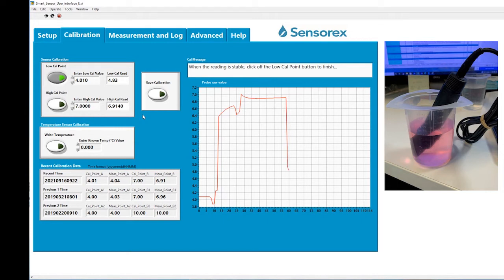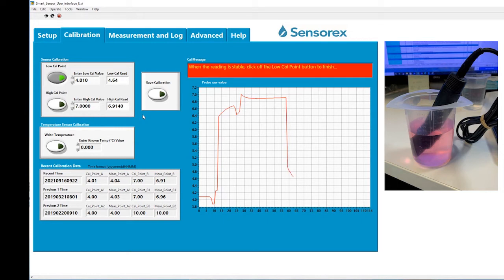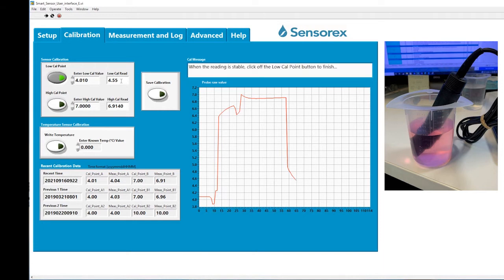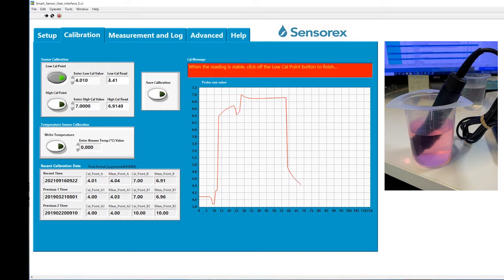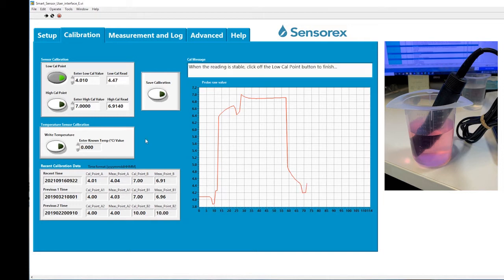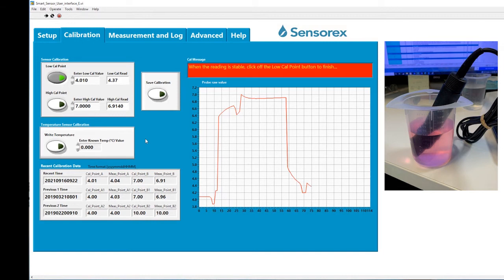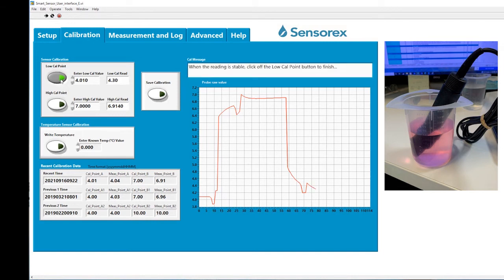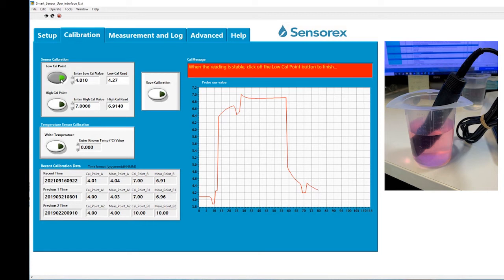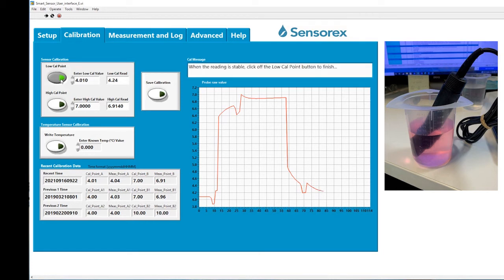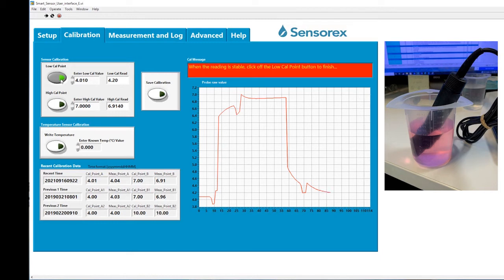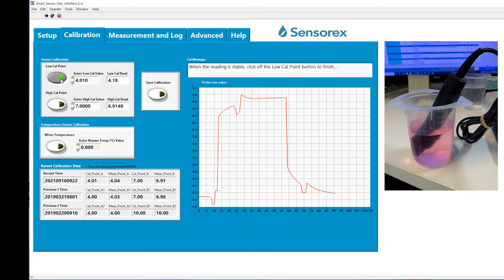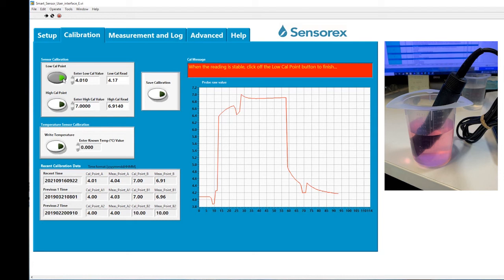As I do that now, the sensor is being monitored. You'll see it in this window here. I'm just going to stir it a little bit because it's best to stir the sensor, get it used to the buffer. Once the sensor stabilizes, we can go ahead and depress the button again, and it will save that value as your low calibration point. I'm just going to give it another few seconds until it stabilizes. It looks stable enough right here, and we're going to go ahead and capture that value.